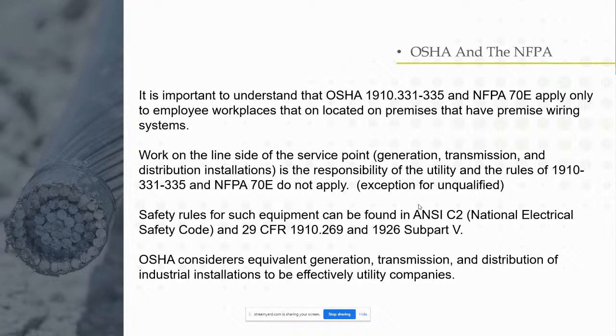Another thing to point out is that when you talk about utilities and the exemption, they make it clear that OSHA considers equivalent generation, transmission, or distribution at industrial locations to basically be a utility company. In other words, if a company generates its own power and has its own substations, distribution, and even T-lines, it's considered a utility as far as regulations are concerned. It doesn't matter if you're owned by a utility or not - if you have equivalent installations, you're effectively a utility company.